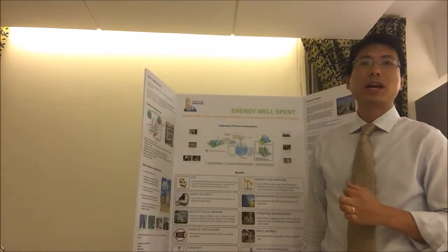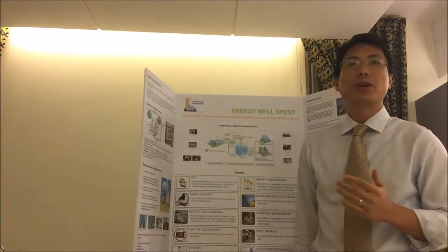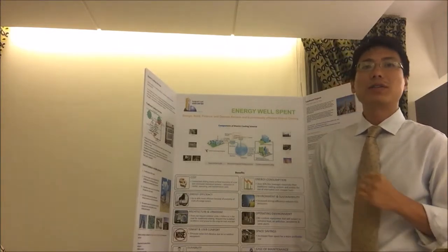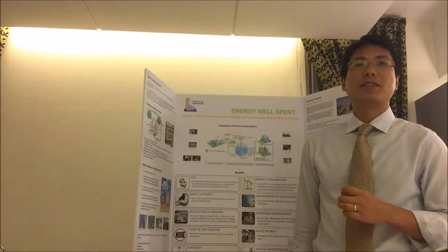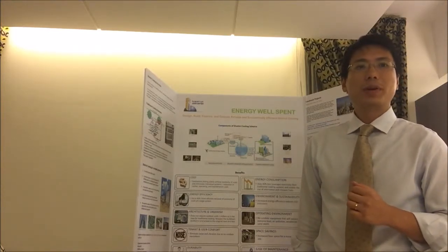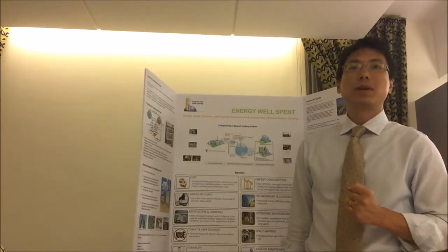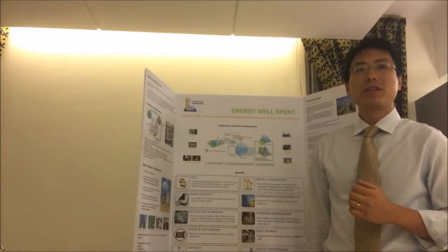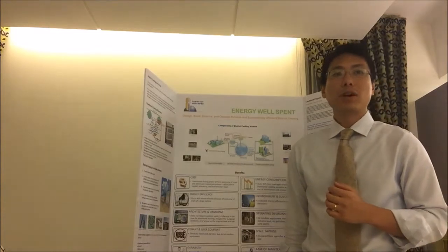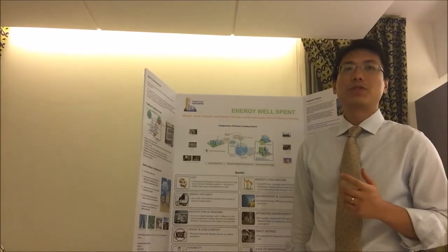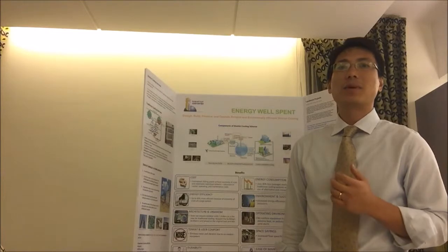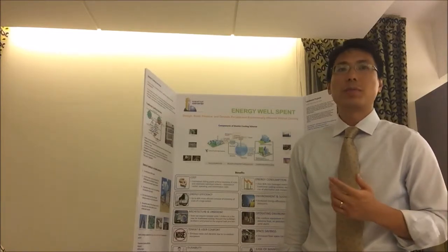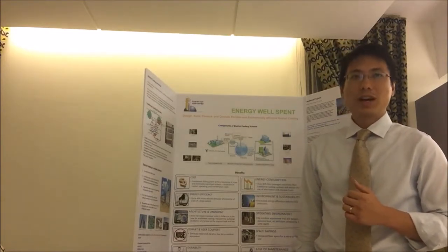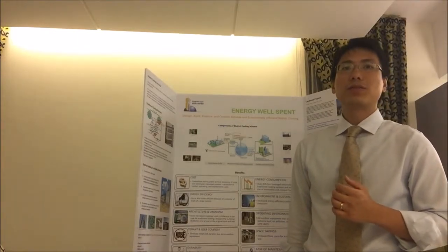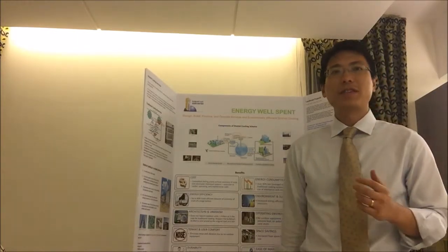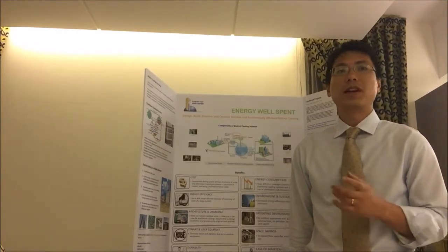District cooling utilizes the chiller, which is also used commercially, but the centralized chillers are industrial grade with high capacity. In a commercial property, each chiller is designed to meet the peak demand, which can be significantly higher than the average demand, so multiple individual units mean significantly higher capacity that is only used during peak time. On the other hand, the central chilling plant is used for many customers, so the ups and downs of various customers may be evened out.